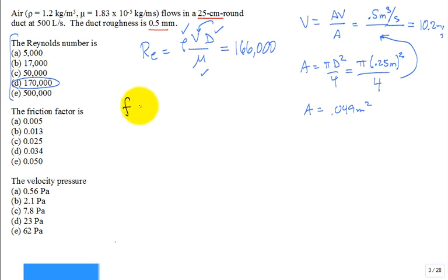the friction factor is found using the Moody diagram as a function of the Reynolds number and the relative roughness. We already have the Reynolds number. Because it's on a log scale on the Moody diagram, it's probably best to put it to two significant digits, 1.7, and then to the power 10 to the 1, 2, 3, 4, 5, 10 to the 5. See that? So it's around 2 times 10 to the 5. That's the Reynolds number. Because it's on a log scale on the x-axis of the Moody diagram, I prefer to put that Reynolds number that way first so I get in the right area.